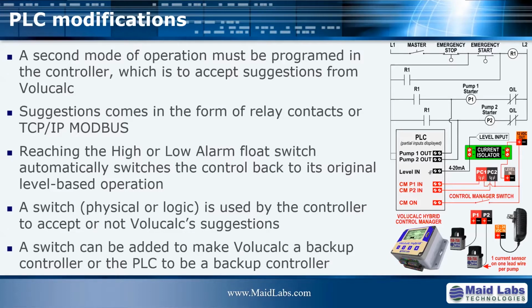That is an easy way to do that with only one analog input. The other way is to connect to the TCP/IP Modbus of our instrument and get that value, and at the same time, which pump should start and when. So that's another way of doing it. Since we're calculating the pump capacities at every cycle, we're able to say which pump is the most efficient, the one with the highest capacity. When the flow rate is low, you run the one that has the lowest flow rate, and when the flow rate is high, you use the other one. So that's another way of doing it.